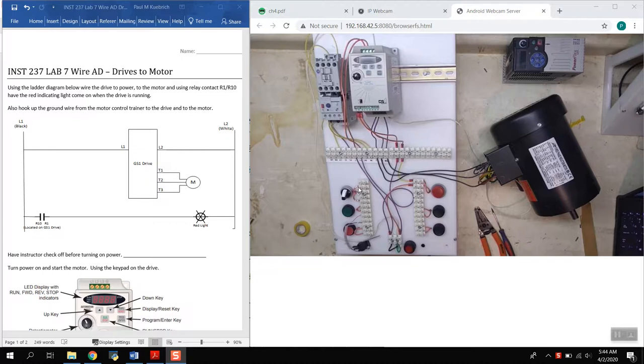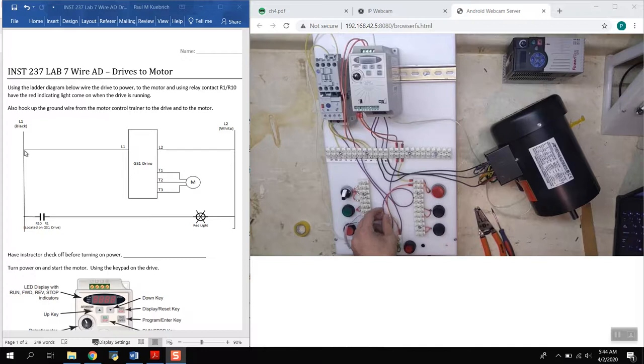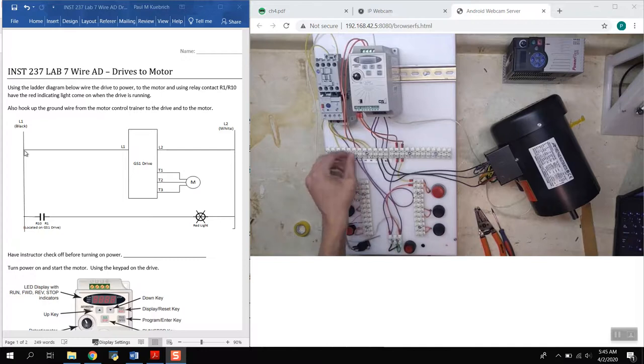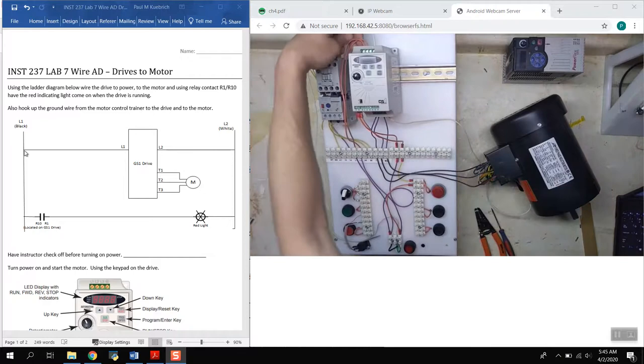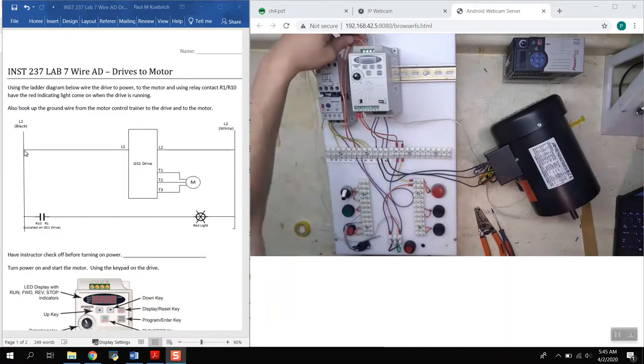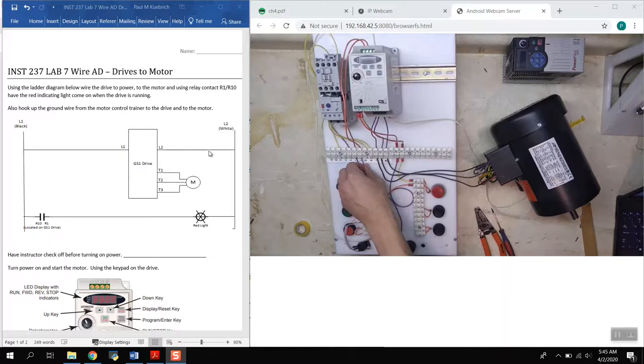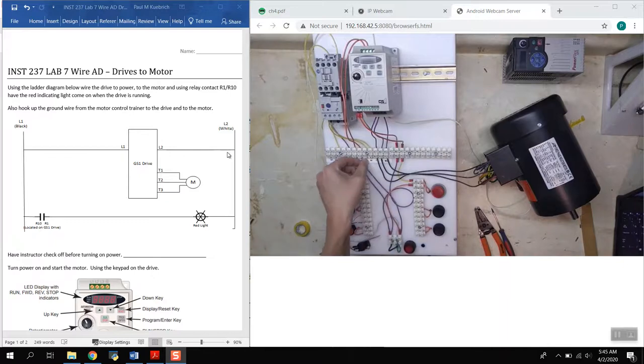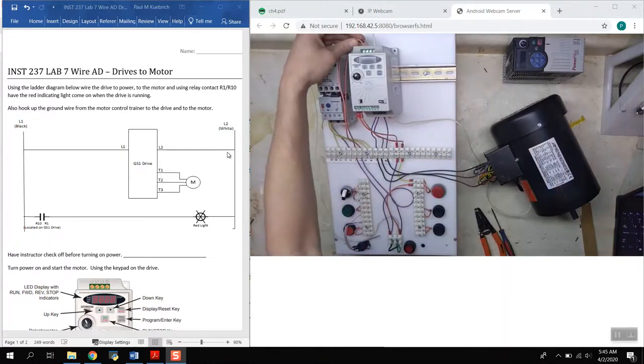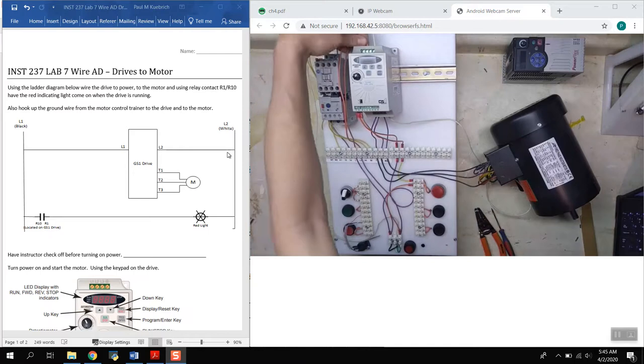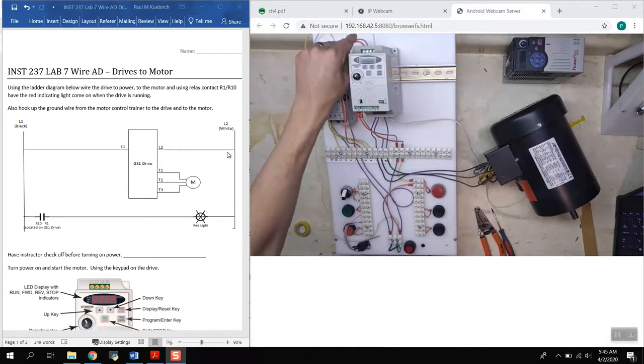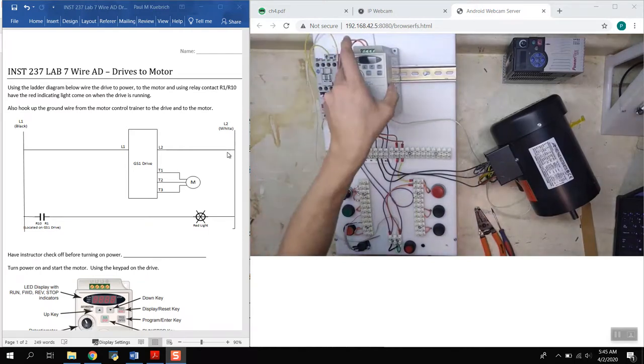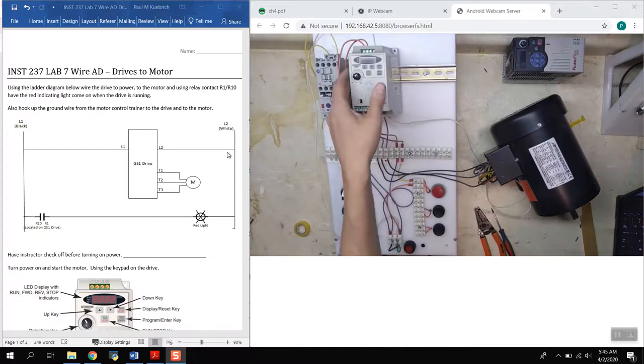So I already wired it up as you can see on this screen here. Starting with the power supply, L1 comes in to the top of the drive here, this is our L1 power, single phase 120 volt power coming into the drive. And then this is our L2 back to neutral coming in over here.